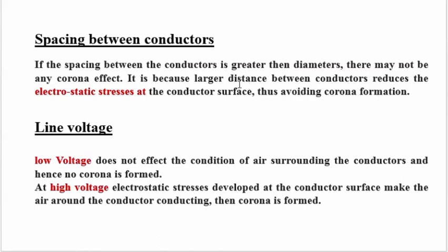Next factor is spacing between the conductors. If the spacing between conductors is greater than the diameter of the conductor, there may not be any corona effect. It is because the larger distance between conductors reduces the electrostatic stresses at the conductor surface, so avoiding corona formation.